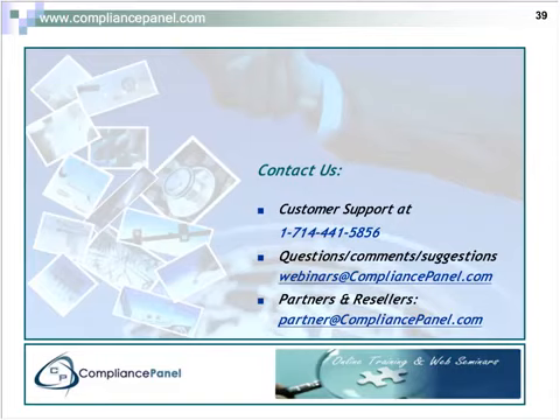So you have to take a good look at what you're marketing, and whether it falls into the category of a medical device. And if you're uncertain, there are ways to ask the FDA, this is what I'm manufacturing, can you tell me what classification this device is? Is it a class 1, which goes from surgeon's gloves, to a class 3, which is a stent that goes into a carotid artery, for instance. It's somewhere in between. And then there's a product code for each one of these.